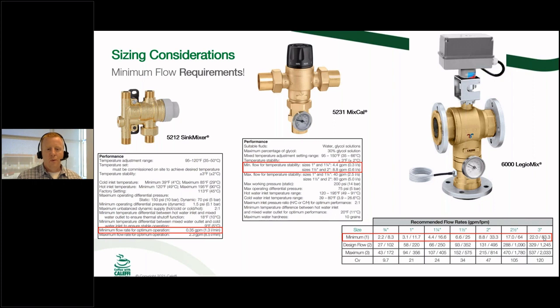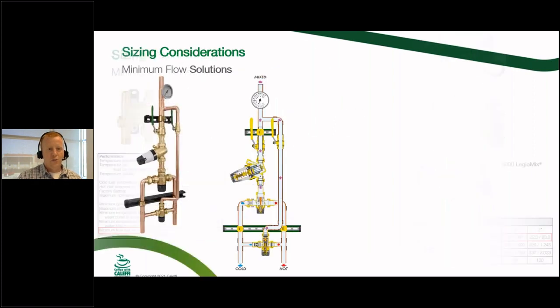Okay, there's a couple of ways that you can do this, and here are the solutions. The first one is, instead of a single mixing valve, you are going to look into a high-low type mixing valve configuration or assembly. This is an assembly that's going to allow you to use a small mixing valve, you've got the little guy right down here, and then a larger mixing valve. During low flow applications, that smaller mixing valve is going to basically do all the heavy lifting. But as the flow increases, the pressure drop is going to increase as well within this small mixing valve. And then on the outlet of this larger mixing valve, you're going to have a pressure reducing valve. So as the pressure drop increases across this little mixing valve, this big pressure reducing valve here is going to start opening up and allowing flow through this larger mixing valve to basically act as a stage 2, or second stage, in order to fulfill the needs of that building.